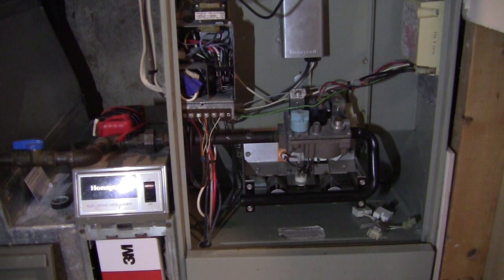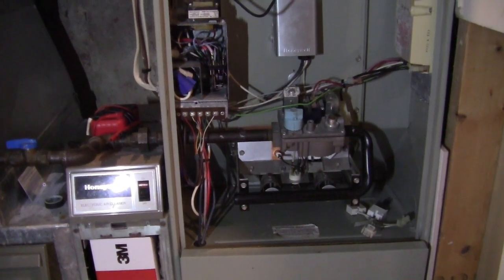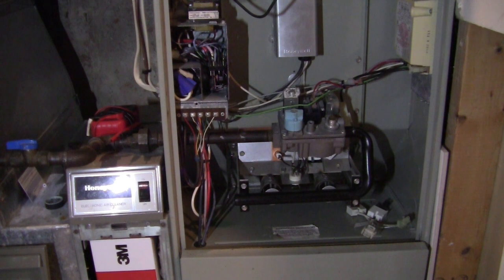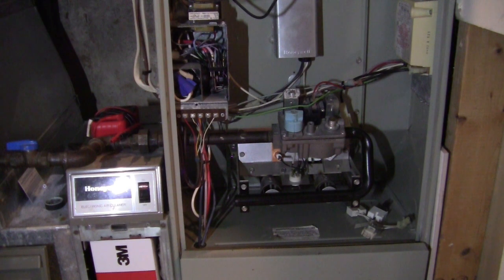So definitely this is different from the oven we use for cooking. When we cook, the fire is in the room. But because we are sitting there watching while cooking, and we might not totally seal our window and door, and in a lot of families we have a fan to suck the burning air to the outside. So the basic unit is the same thing: burning gas. But the oven releases the burning air into the living area. This furnace never and should not release any burning air to the living area.